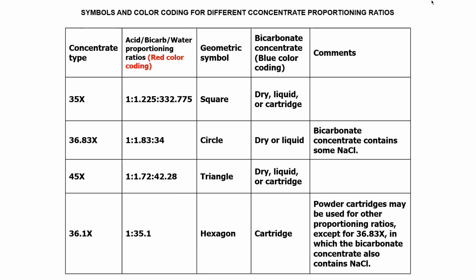What happened when the 45X concentrate was plugged in to that 35X formulation, you had enough ionic concentration in the acid to achieve a working conductivity that didn't put the machine in alarm. The whole facility's population was actually treated for severe acidosis because they were dialyzing on acid only. And that's when the manufacturer said that you have to now do conductivity and pH. That's where that rule came from because of that one incident.